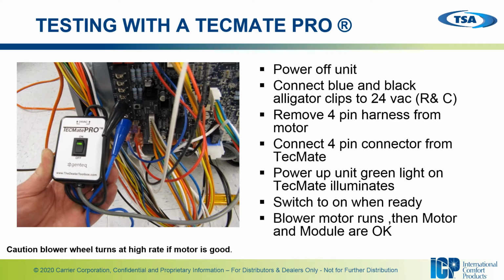position when ready. All right, if the blower runs, then the motor and module are okay. You know it's a signal issue coming from the control board. If the blower does not run, then we know we have an issue in the motor or module.